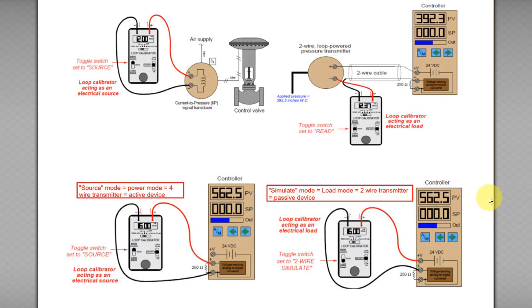Hello, today I am going to discuss about the loop calibrator: source mode, read mode, and simulate mode. A loop calibrator, sometimes called a signal calibrator, is a calibrator usually used by instrumentation technicians to inject a signal to the circuit, transmitter, or controller for simulation or testing purposes.